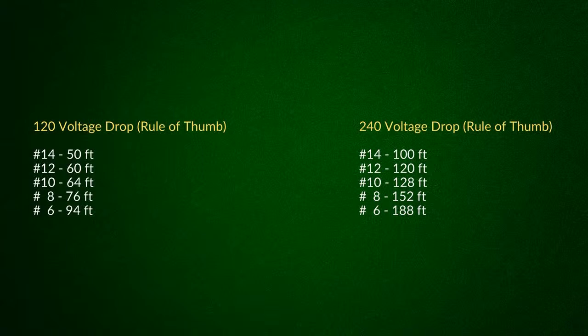So these are things I'd tell people to look at: the table at that time was based on a 1,000 foot run, that's what the averages were. But once you get at 100 foot or more, the rule of thumb at that point is you need to apply a voltage drop.